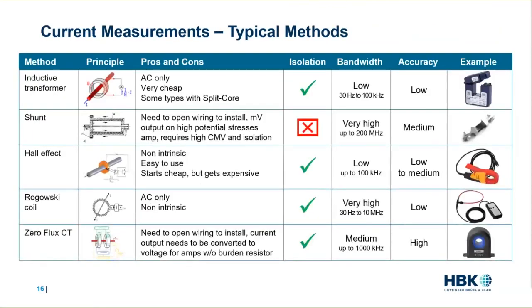Now, often measuring current is more challenging, especially when it comes to accuracy. In fact, some of the more typical methods for measuring current include inductive transformers. However, they only offer AC measurements, low bandwidth, and low accuracy. Shunts, although they offer very high bandwidth and medium accuracy, are challenging since they not only require opening the wiring to install, but they require isolation. And they place stress on the amplifier due to a small millivolt output being measured on a high potential.